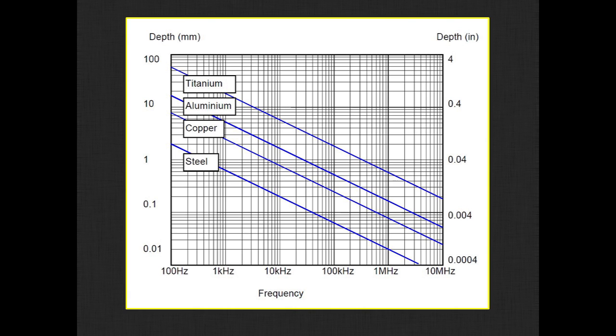Here's a graph showing a little bit about this permeability issue. On the horizontal here we have the frequency. You can operate these probes at different frequencies. We happen to use about 200 kilohertz. Some of the competitive products get closer to one megahertz. These are the different materials and again titanium is the least permeable material and steel would be the most permeable material. So if we're operating at about 200 kilohertz here in steel, what you'll find is that we're only penetrating with this magnetic flux down into the material only a couple of thousandths of an inch. So it doesn't penetrate very far.